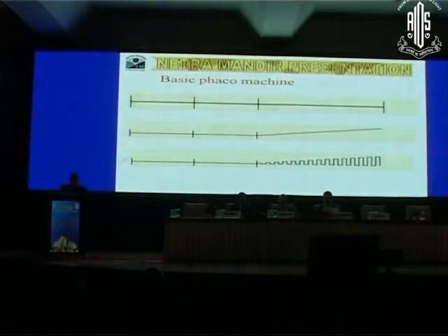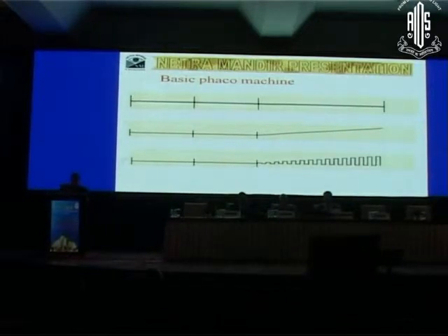As you understand very well, we started with a basic phaco machine where there was something like an all or none phenomenon, where the moment you go to foot pedal position 3, you have the energy delivered to the preset level. From there we went into the second phase where we had a linear delivery of the energy. That is, as you depress the foot pedal more and more in foot pedal position 3, the energy starts rising, from where we came to the pulse phaco.